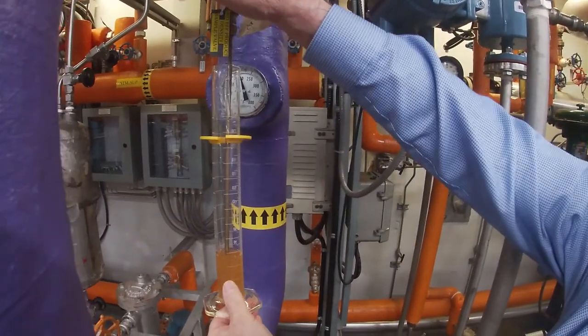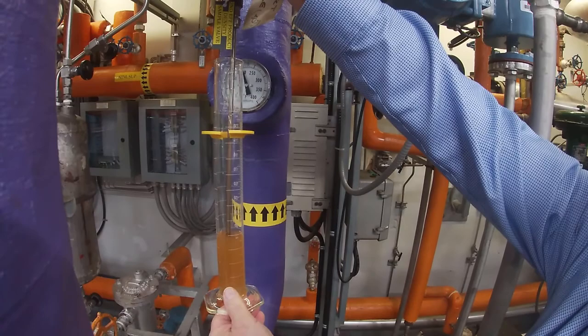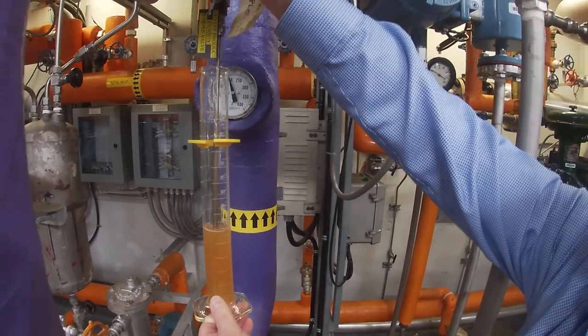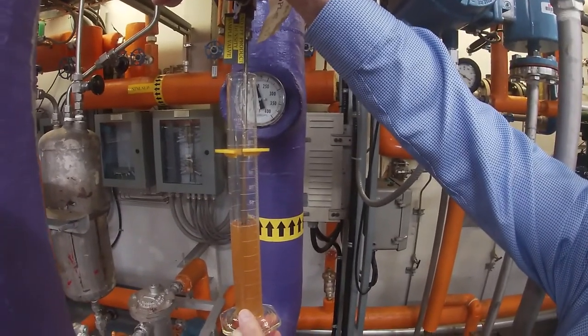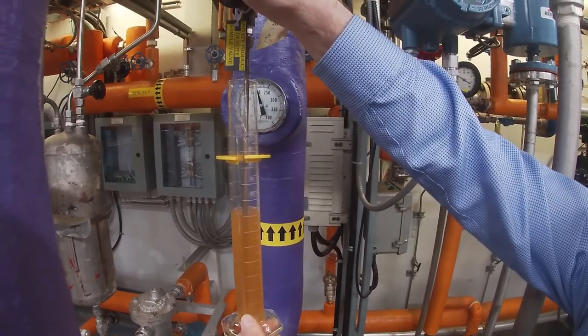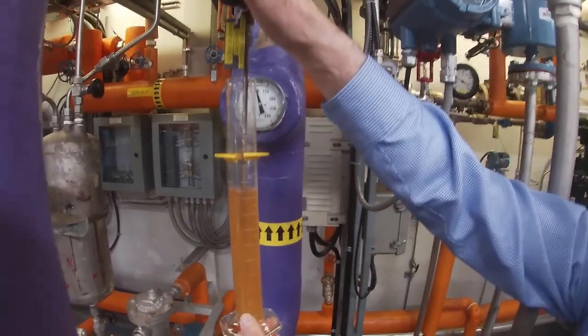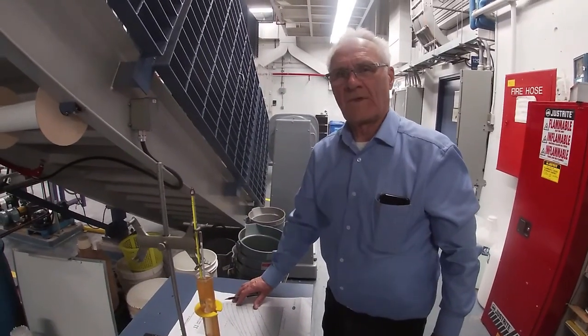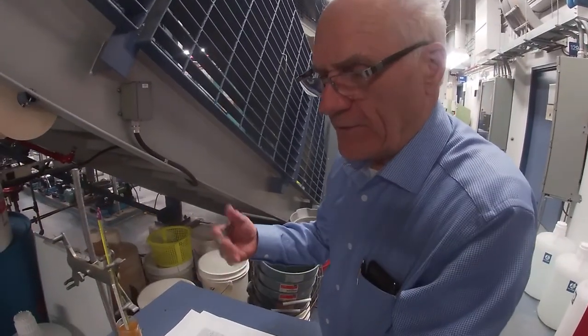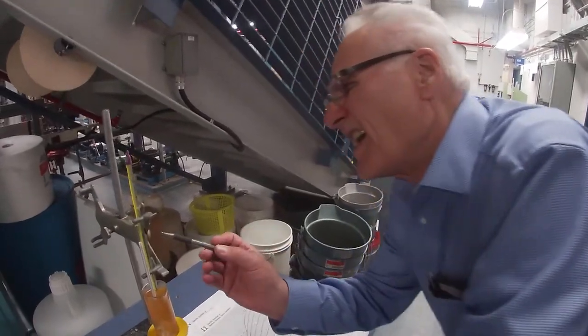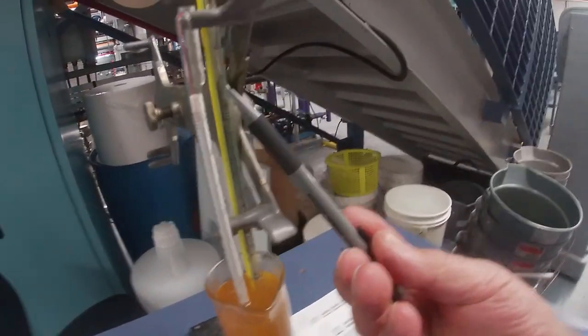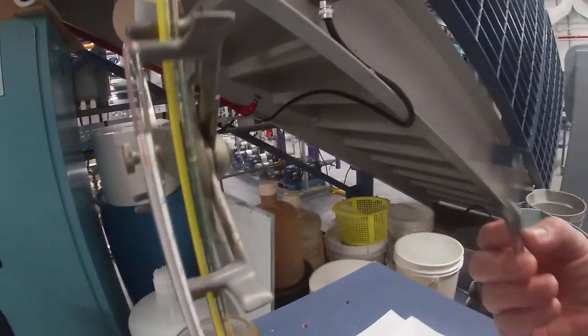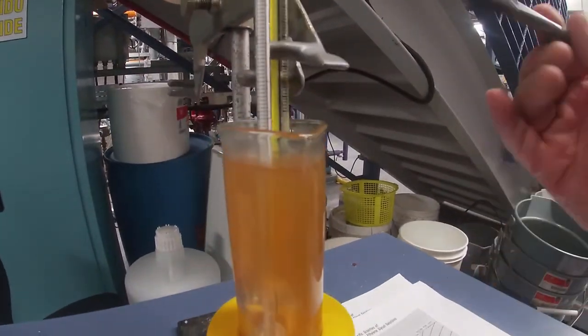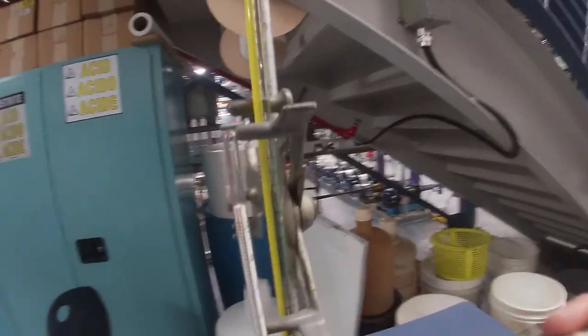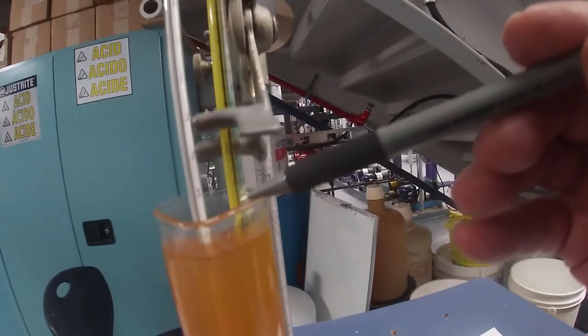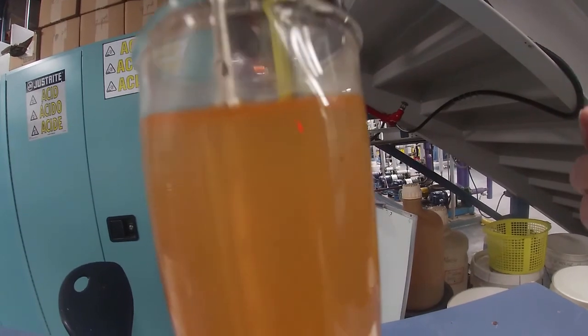You can see it's quite a bit thicker and browner. And this should be up at, ideally, 50% ethylene glycol. Okay, we're going to measure our sample that we've taken from the second effect evaporator. Currently, the temperature is sitting at 150 degrees Fahrenheit. The temperature will be dropping because this is going to be cooling down. The hydrometer is sitting at 1.36. Wow, 1.355.